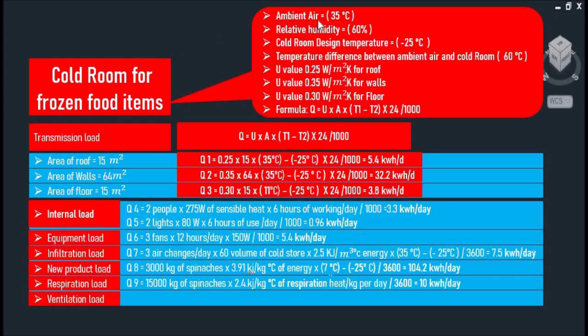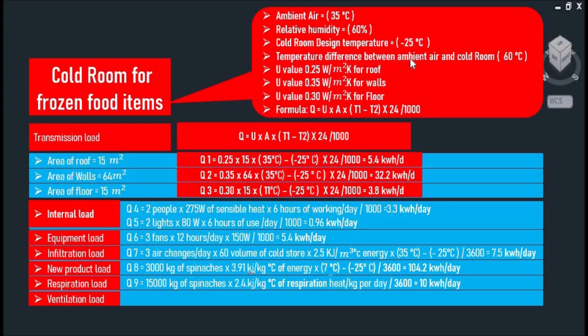The ambient air is 35 degrees Celsius at relative humidity of 60%. The indoor design temperature is negative 25 degrees Celsius, and the temperature difference between ambient air and cold room is 60 degrees Celsius.